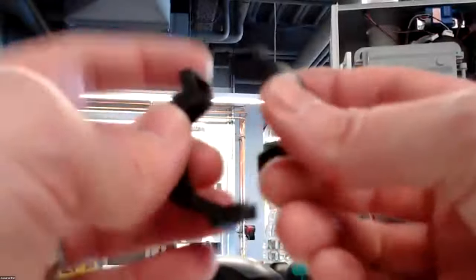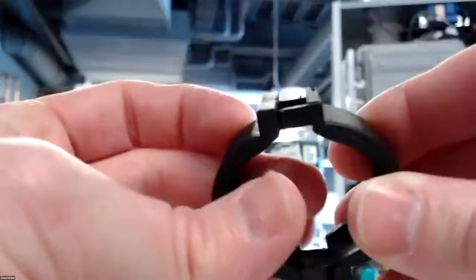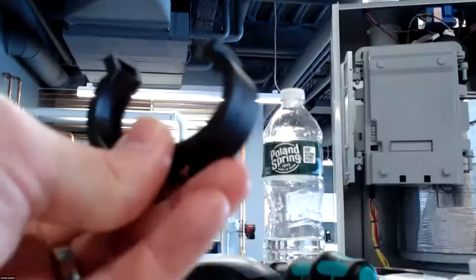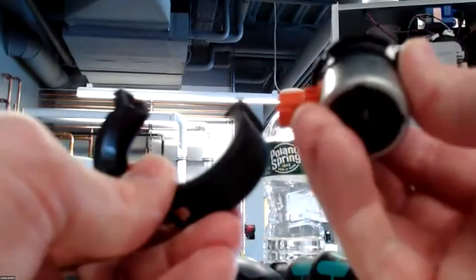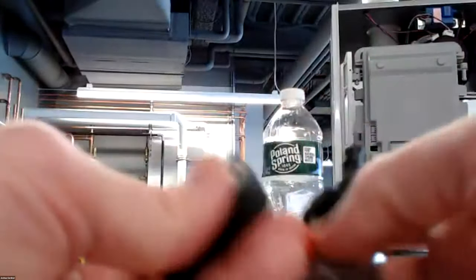So this clip, a couple things to note, has two little plastic clip things that lock into here. If you're removing it and you accidentally, or you really torque on this and you break these, don't worry about it, because if you're replacing the solenoid, it comes with new clips. So if you end up damaging this or breaking it, you get it with the replacement solenoid valve.